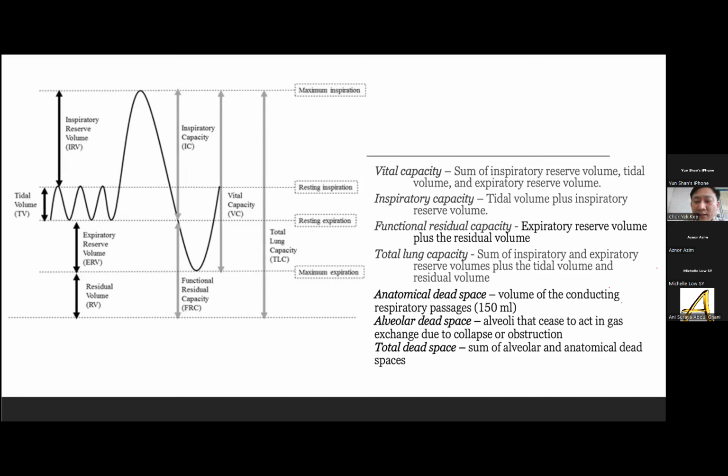The other thing is that, yes, expiratory tidal volume is the most accurate measurement of tidal volume, but the problem is that if the tubing is leaking, then it is no longer accurate, because the air escapes to the side and you're not able to measure accurately.